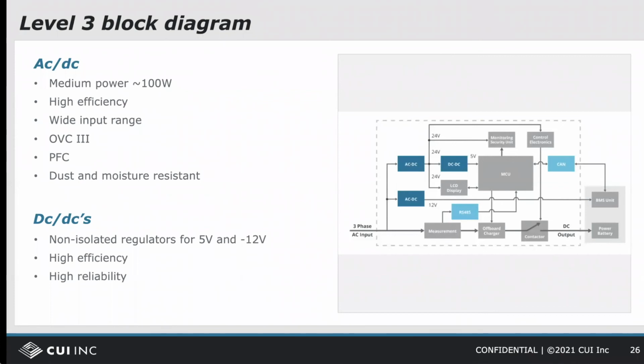To support the additional functionality, a larger power supply will be needed than that of the level 1 and level 2 chargers. These chargers could require 100 watts or more from the AC to DC. The voltage may also be increased to 24 volts, and a second power supply may also be required to power the BMS. The power supply in this case must have a wide input range so that it can operate off of three-phase line voltages up to 480 volts.